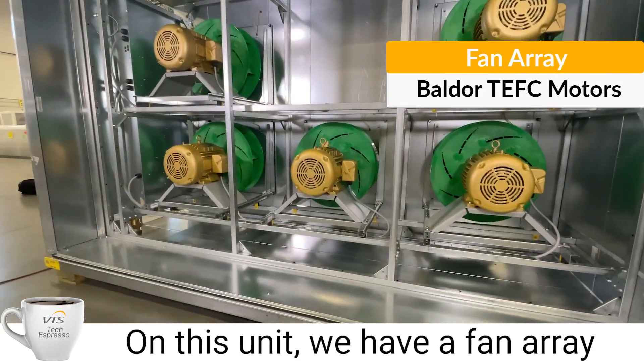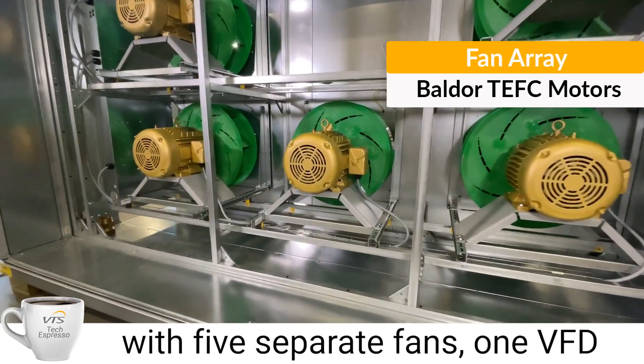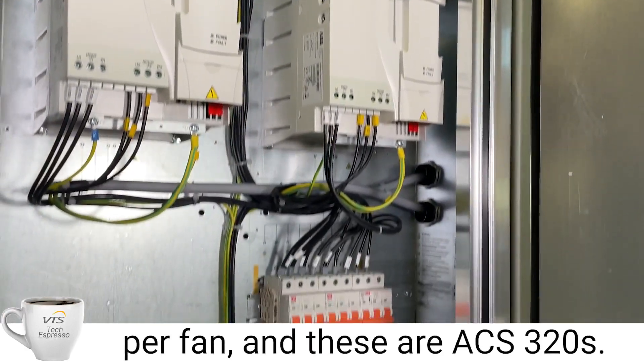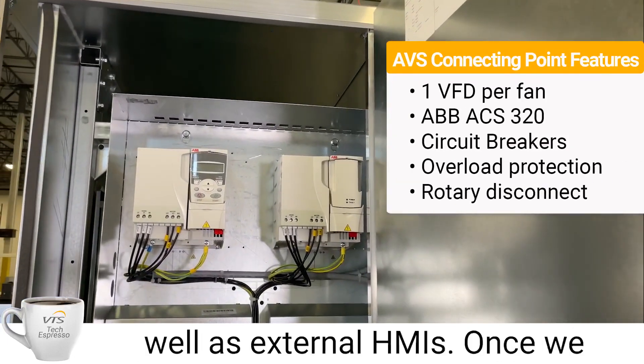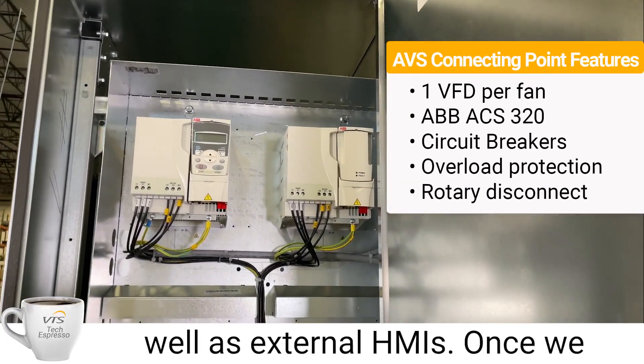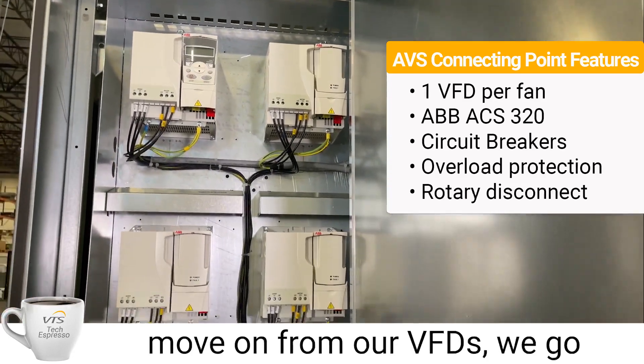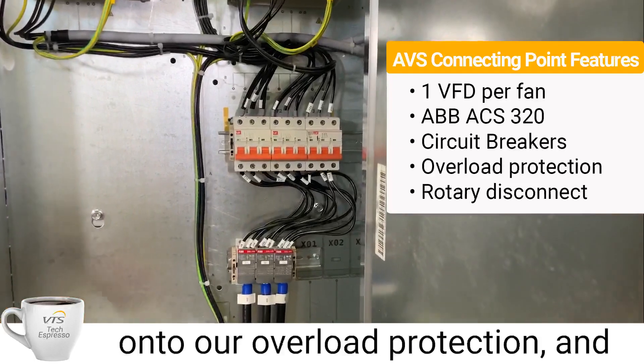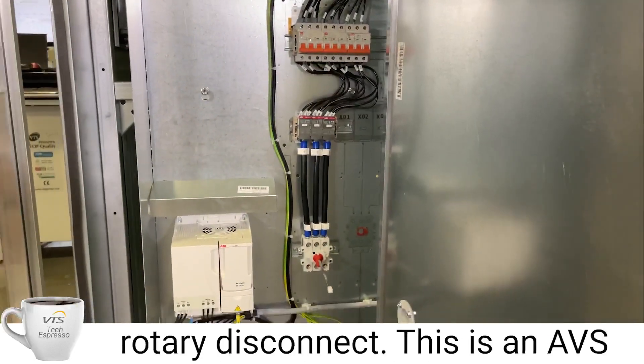On this unit we have a fan array with five separate fans, one VFD per fan, and these are our ACS 320s. On each one of them we have an option for a removable keypad as well as external HMIs. Once we move on from the VFDs, we then go into our circuit breakers and on to our overload protection and finally our point of power and rotary disconnect.